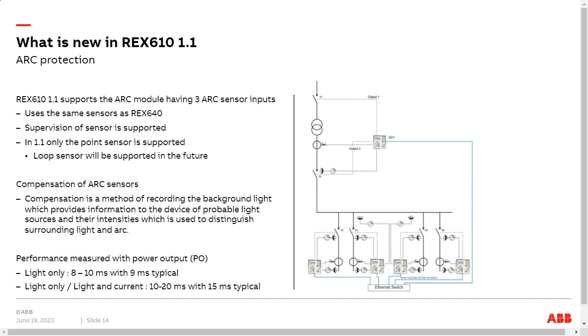And in this picture, you see, for example, an arc system with several REX610s connected, in this case using GOOSE, so you can also trip the incomer depending on the selectivity criteria.